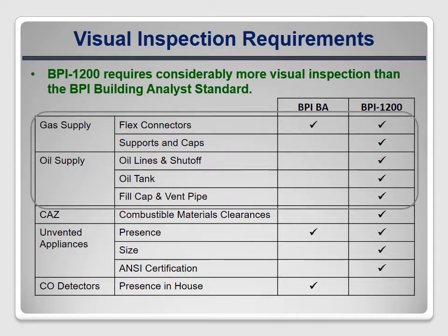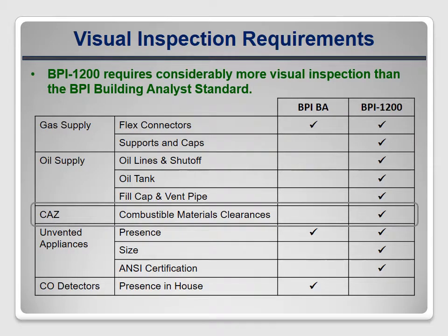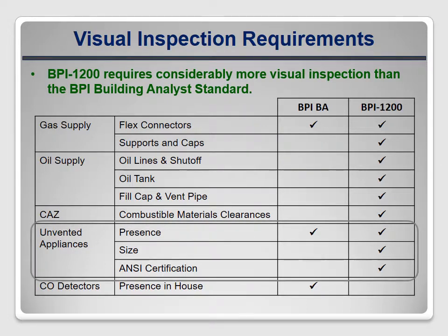BPI 1200 requires a detailed inspection of the entire fuel delivery system, while the BA Standard only mentions evaluating gas flex connectors. BPI 1200 clearly states how to inspect the combustion appliance zone for inadequate clearance to combustible materials, which is not mentioned in the BA Standard. BPI 1200 also requires a detailed evaluation of unvented appliances, including sizing and certification info from the data plate, whereas the BA Standard only requires that these appliances be identified and disabled prior to weatherization work.